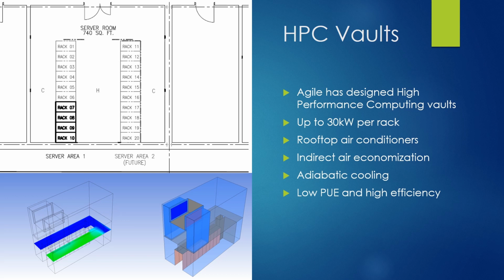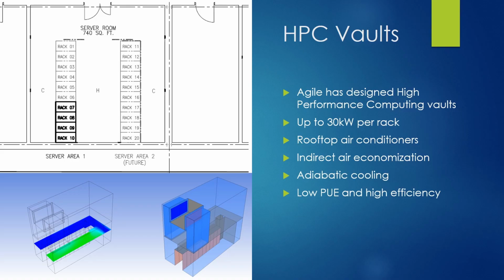And the way that we know that's true is that we actually ran it through our own computational fluid dynamics model, which in a weird kind of circular logic is a high performance computing application that runs on the cloud. So we're actually using what we're talking about. But we designed it with these very, very large return and supply plenums so that the static pressure on the fans can be pretty low, but we still get that high efficiency of the air going through.